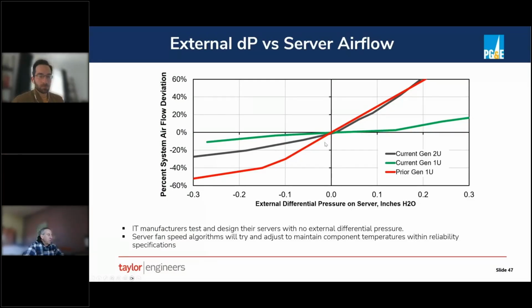I don't know the history behind this data and what a prior generation 1U server is versus the current generation. I guess apparently newer servers are more resilient to negative pressure, and so maybe that 600-700 feet per minute can get pushed up a little bit. But either way, you want to try not to let the velocity get too high.